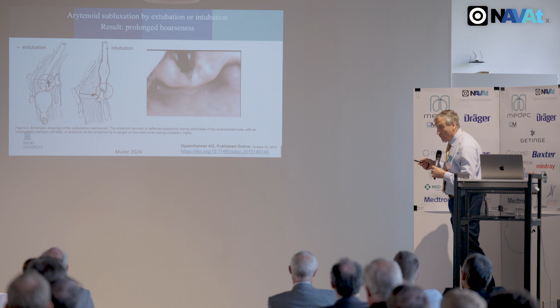But the leakage, well, I was already working on that a long time ago when I was investigating the impact when the TaperGuards came on the market. I figured out if you put gel on the cuff, it helps also to fill up, because otherwise the high volume, low pressure cuffs always leak immediately. With gel, you can postpone that a little bit. Nevertheless, there will still be some leak, as you will see there with methylene blue. The MicroCuff also came on the market. The MicroCuff is a very, very ultra thin membrane, and it will not give any plica, so that means that there will not be plica as what you will see here in this one.